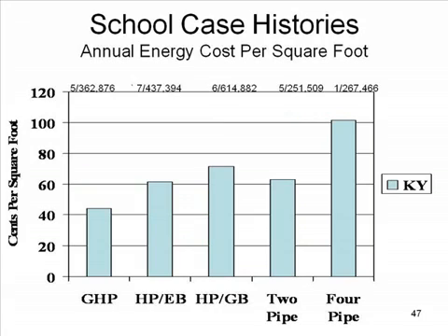More school histories. This was in Kentucky. A study done with different technologies. Geothermal heat pump on the left, heat pump with electric boiler, then heat pump with a gas boiler, 2-pipe, 4-pipe, and you want to take a look at these things, because as utility or as fuel costs change, you'll want to take a look and make sure that this is going to suit your purposes. Lower first cost, lower operating cost, the best thing for the building owner.